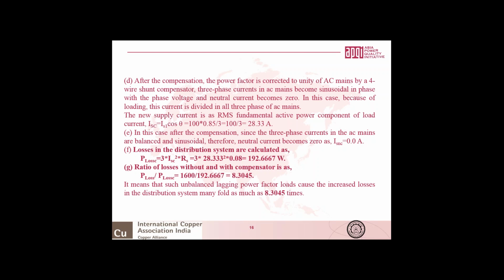So taking the ratio of the losses without and with compensation: without compensation losses were 1600 watt, and after the compensation the losses are 192.67 watt. So the ratio becomes typically 8.3, or you can say the losses become around 12 to 13%. So these are reduced to 12 to 13% only, from 1600 watt to 193 watt or so. It means that unbalanced lagging power factor load caused the increased losses in the distribution system manifold as much as 8.3 times compared to the sinusoidal balanced unity power factor loads. So this is a first example.